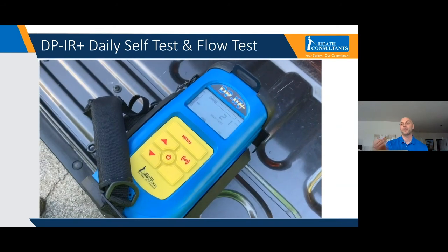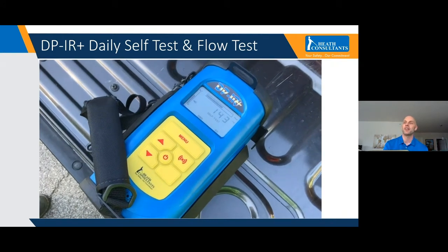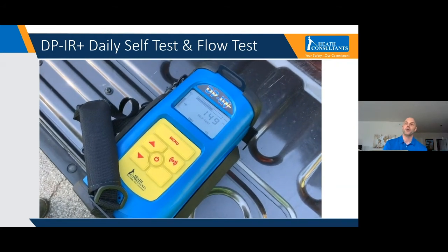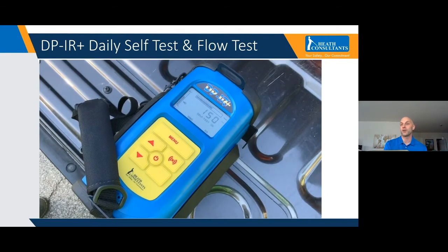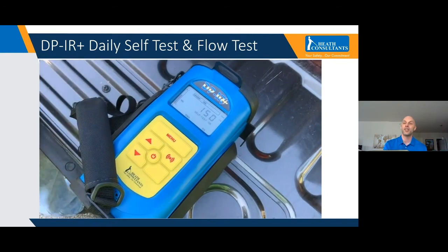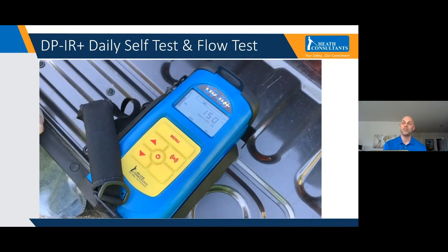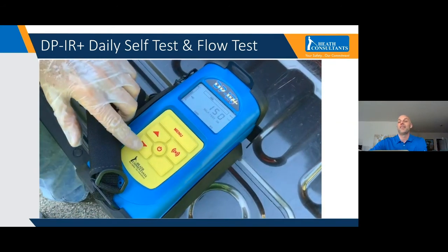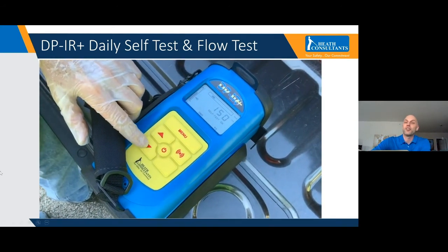Then it takes the cell out of the light path and puts it back in, and you can see the numbers going up again. This is the corrected value. As a user, you don't really need to focus on that. All you're looking for is for it to say self-test OK. You saw that took about 30 seconds. That's really all you do for the calibration procedure on this one.